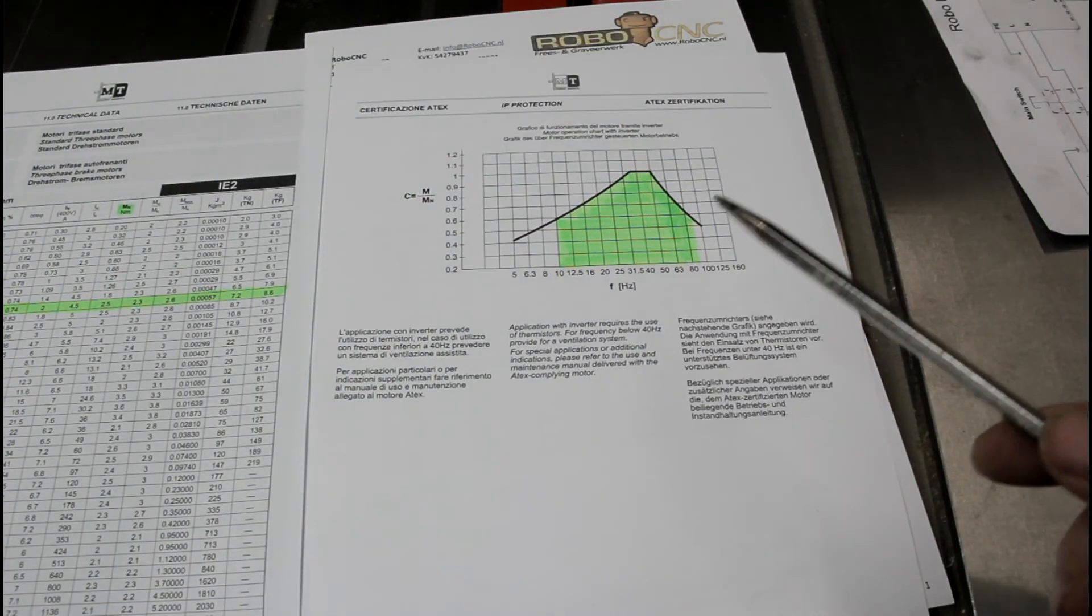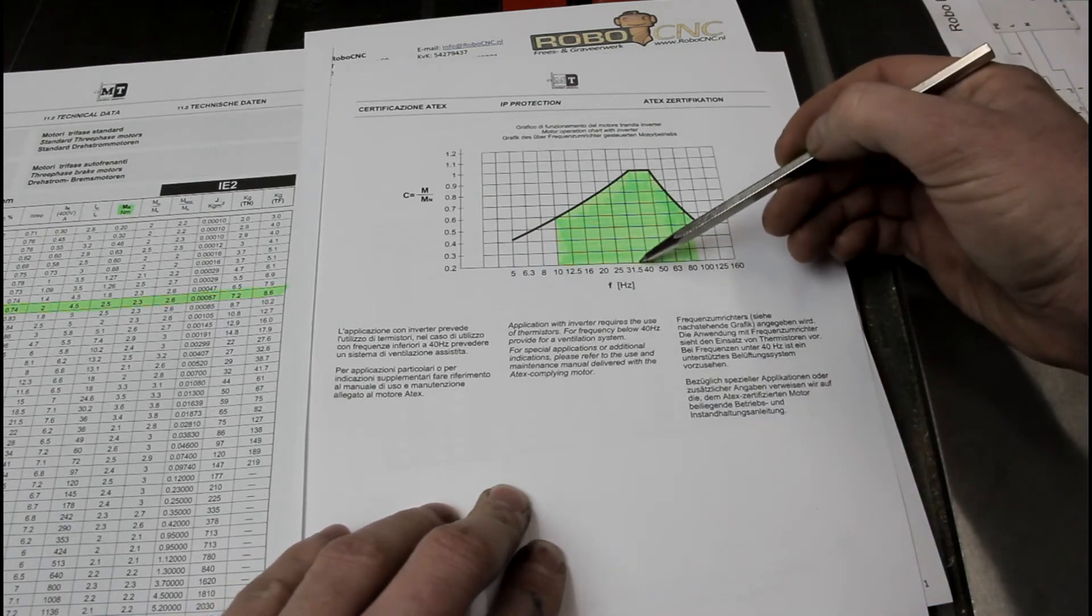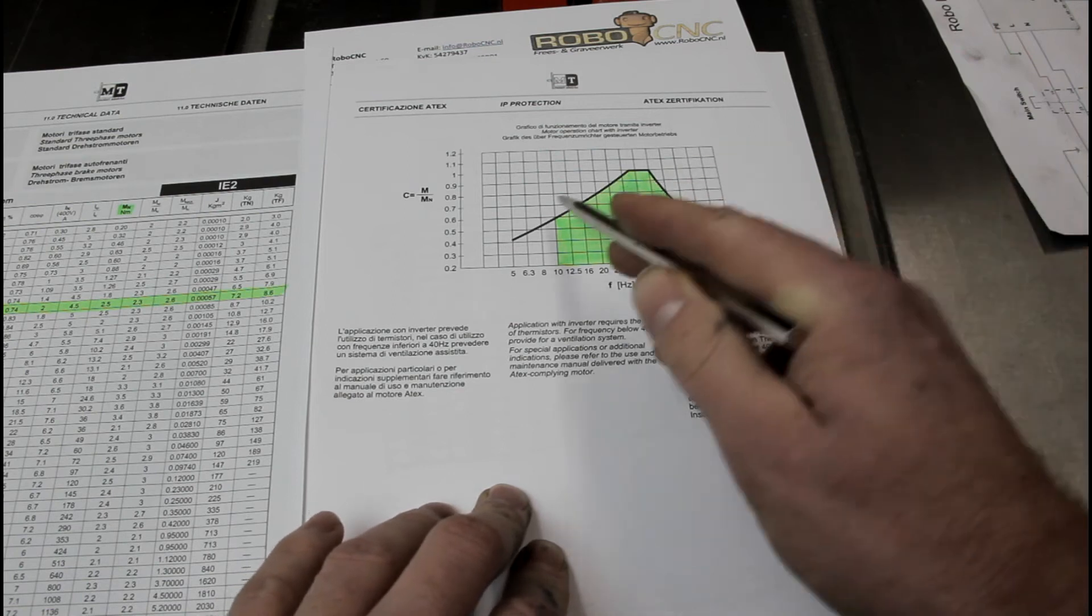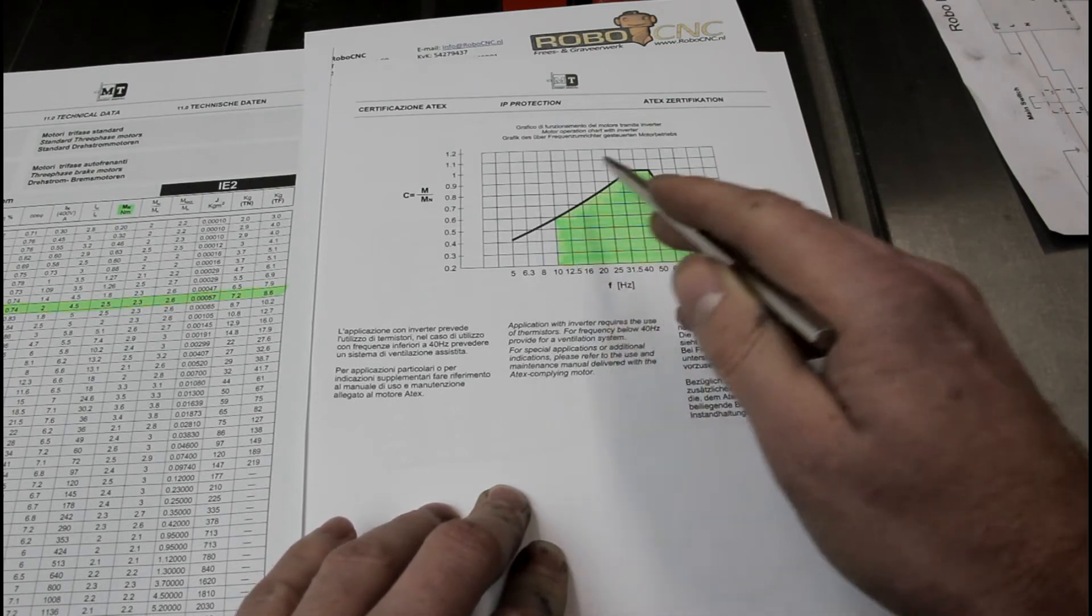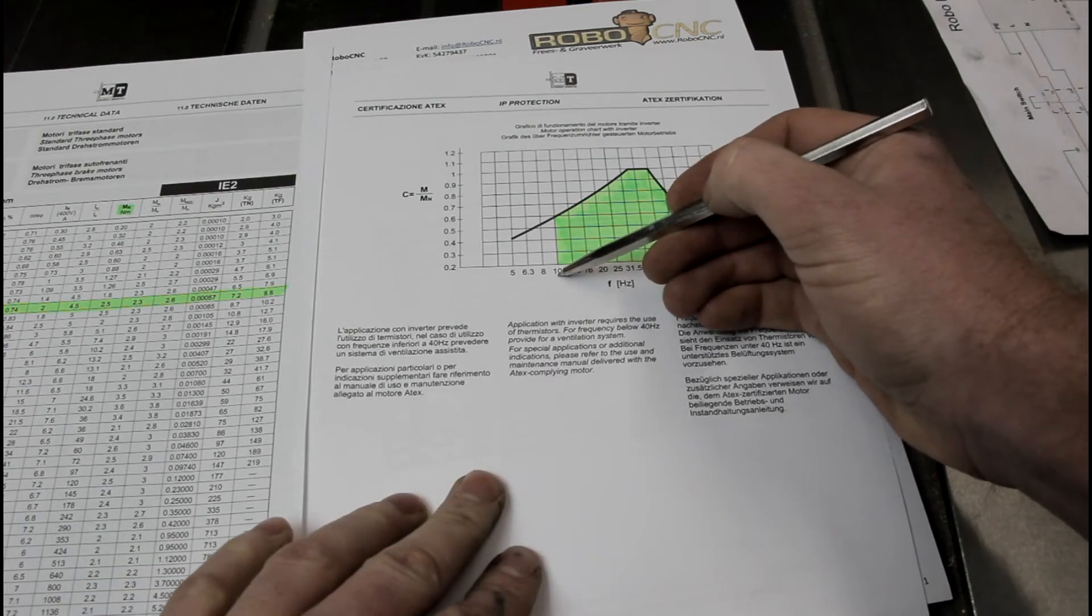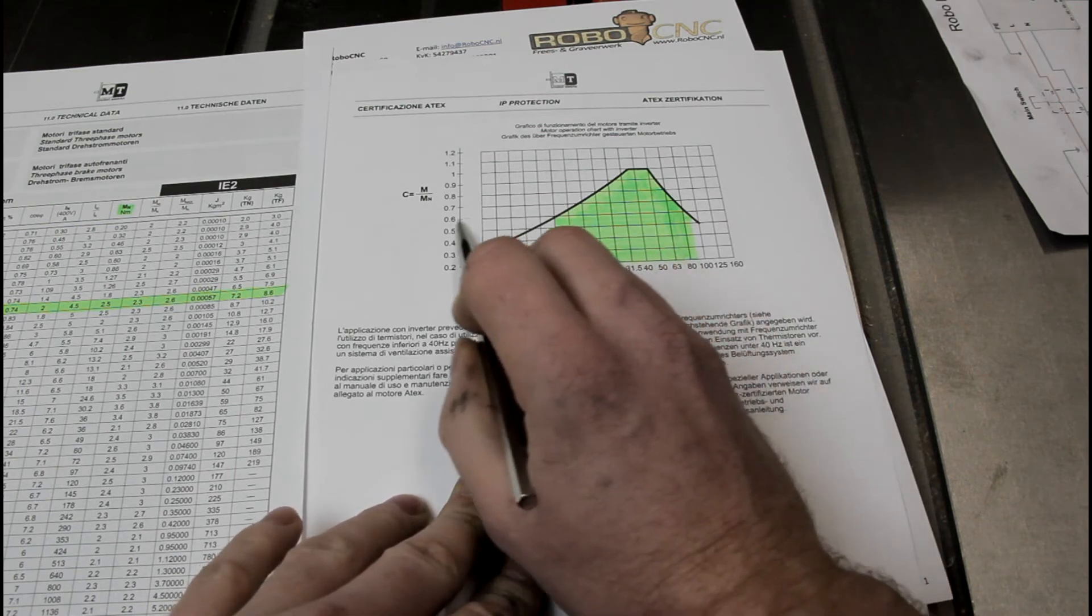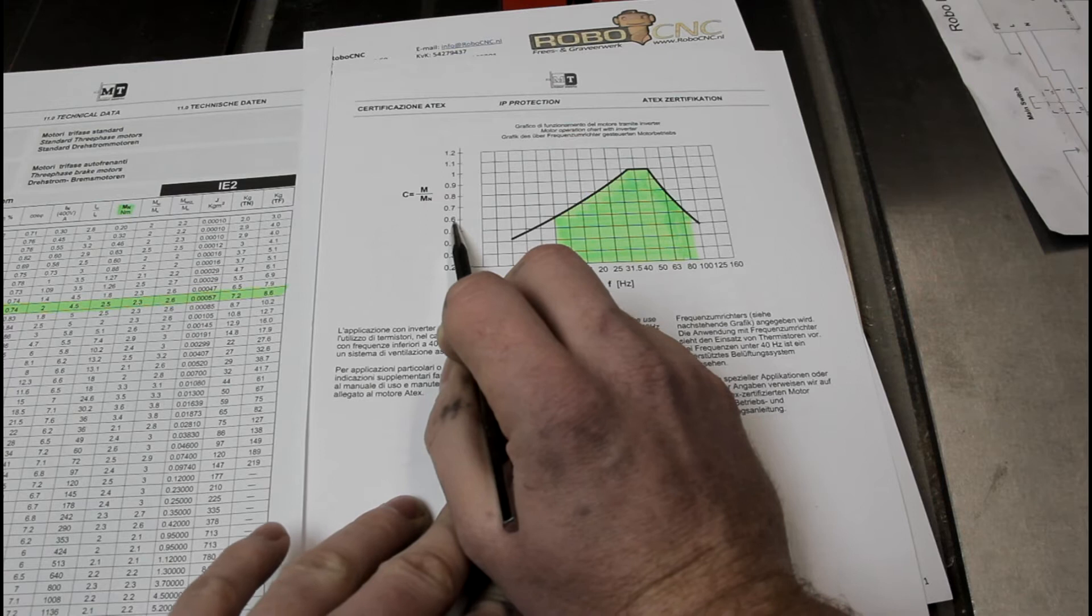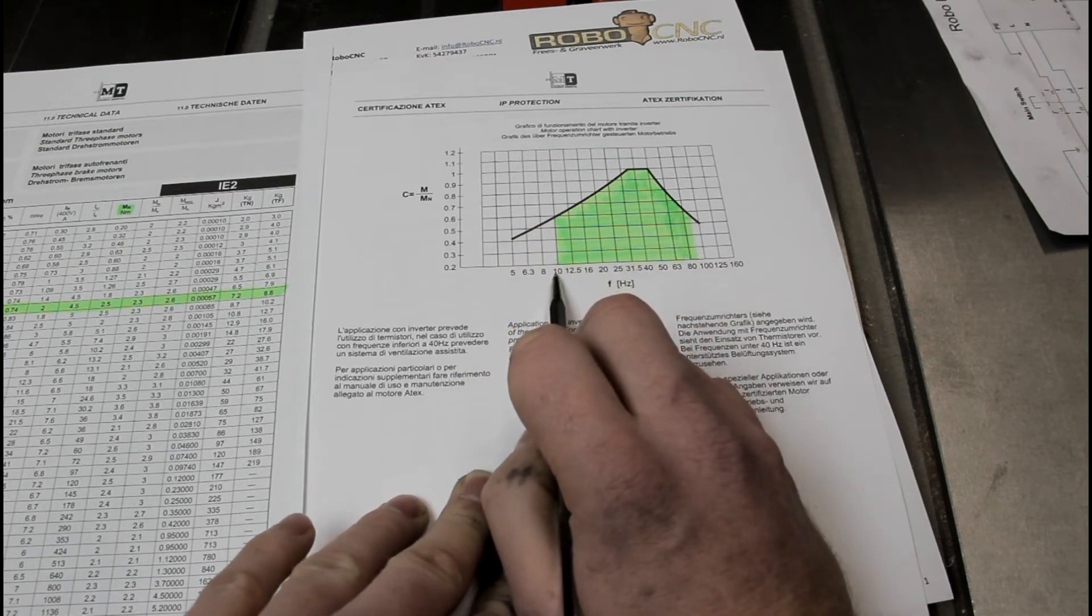So on this page, we can see that the nominal torque is only available to us between let's say 35 hertz and 50 hertz. If my frequency is less than 35 hertz, so if I ramp it down, you can see the torque drops. And same applies above 50 hertz. For example, at 10 hertz, if we set the speed at 10 hertz at the motor, we only have 0.6 factor. So the nominal torque is 2.5, so multiply it by 0.6 and then we have the actual torque at 10 hertz.